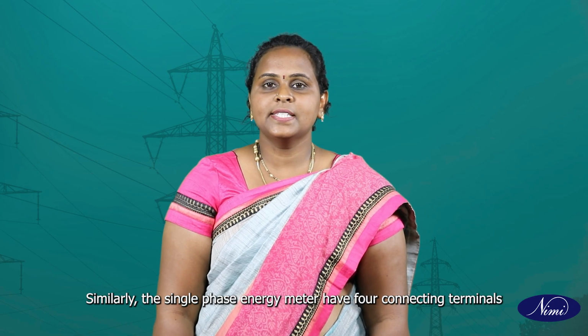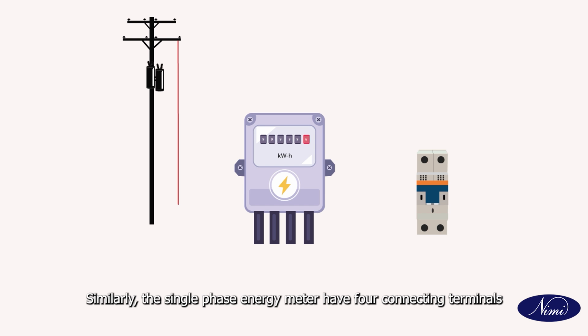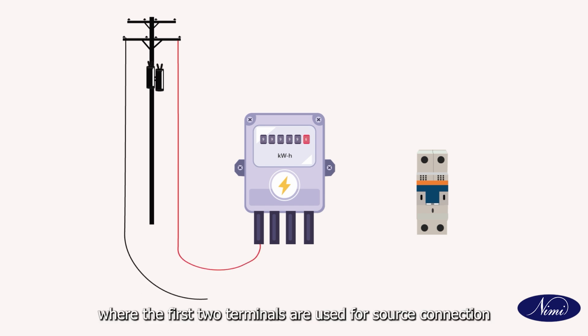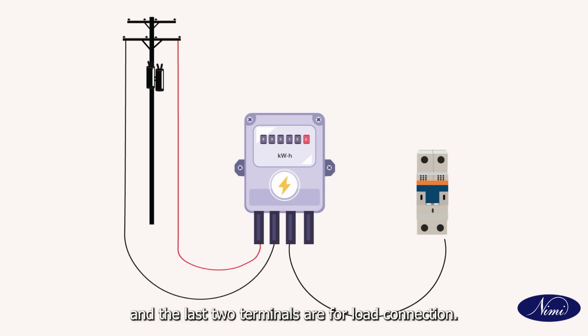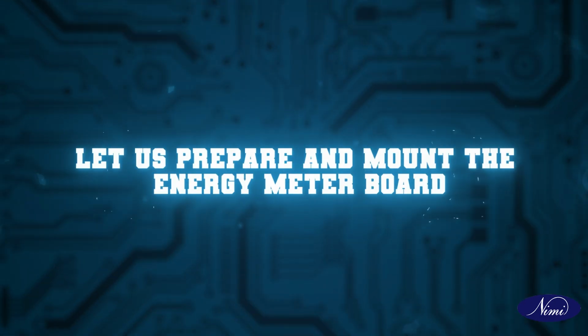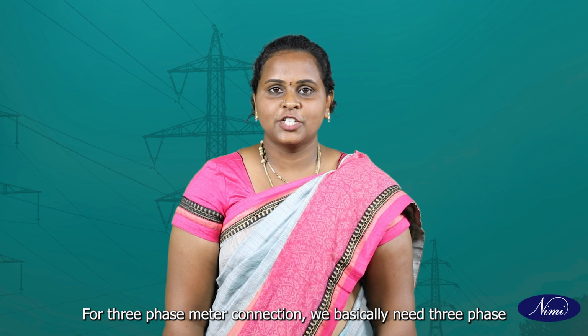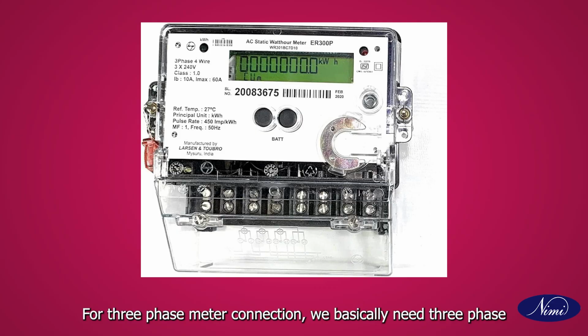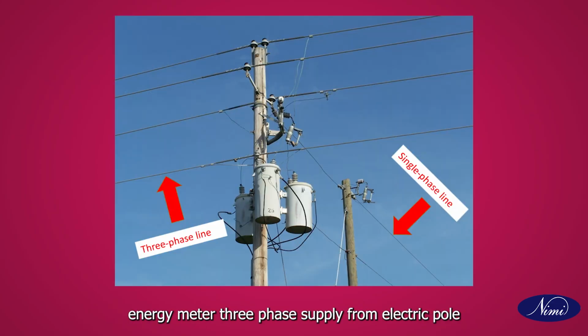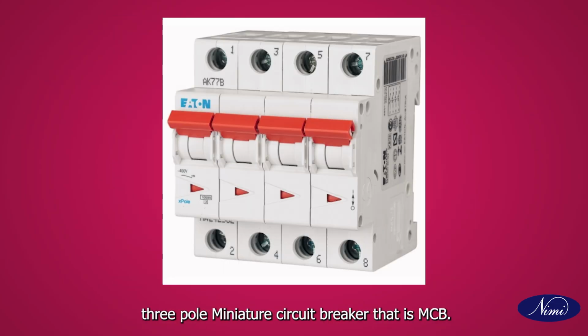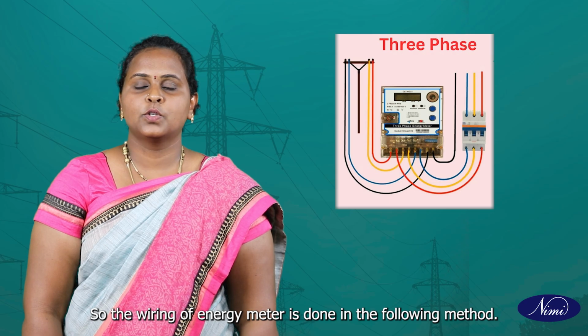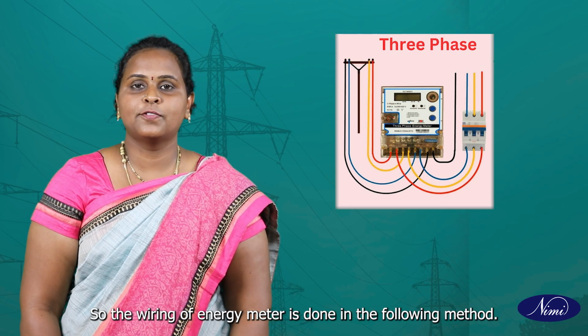Similarly, the single phase energy meter has 4 connecting terminals, where the first 2 terminals are used for source connection and the last 2 terminals are for load connection. For 3-phase meter connection, we basically need 3-phase energy meter, 3-phase supply from electric pole, 3-pole miniature circuit breaker, that is MCB. So the wiring of energy meter is done in the following method.